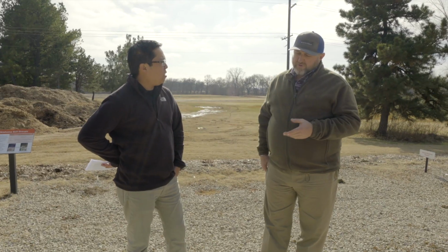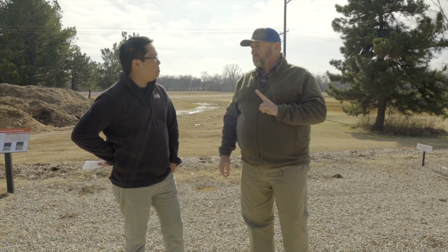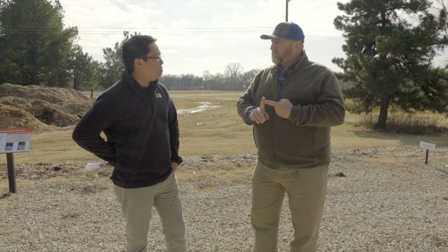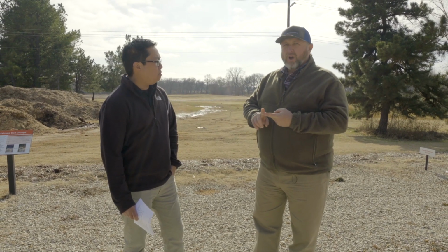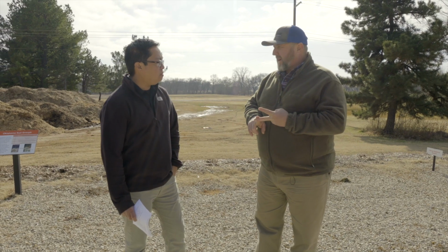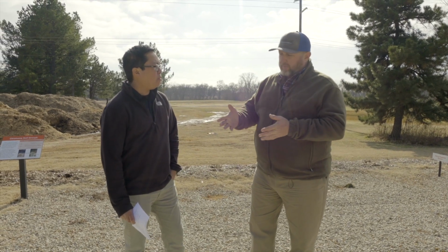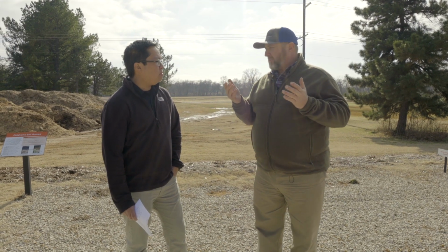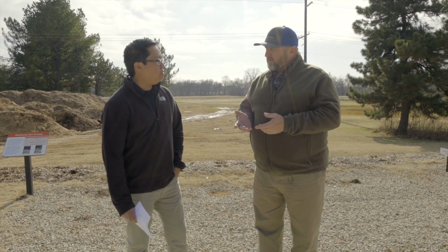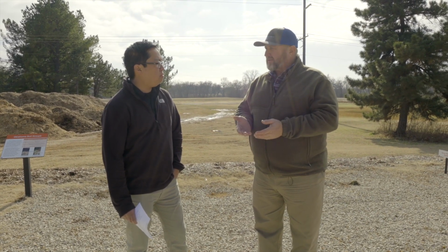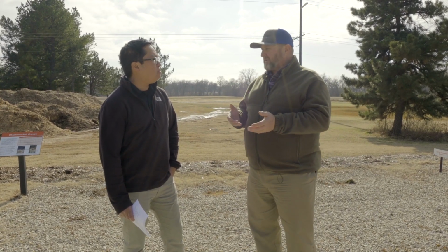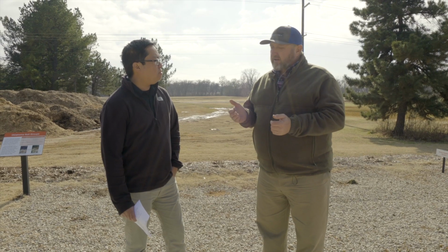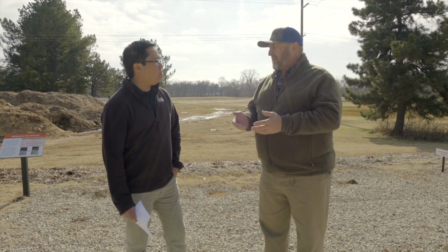On most systems, there's only two things that can cause an alarm. The air compressor is not running, or it's not producing the right air pressure, or you have a high level situation, high water. Your pump is out, or you've used a lot of water, something's stopped up, and it causes the high level float to come up. That's one of the alarms you can get. The other one's going to be your air compressor. It has a pressure switch on it. It sees that it has at least 1.5 to 2 psi depending on where it's set. If it doesn't see that kind of pressure, it gives you an alarm.